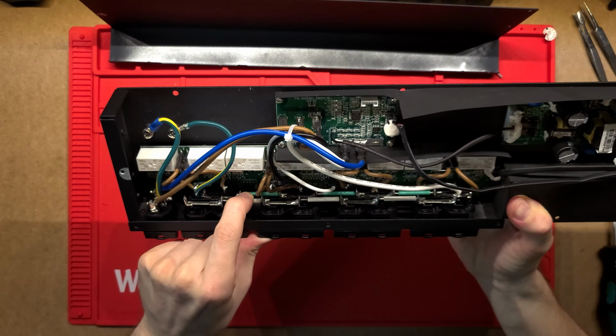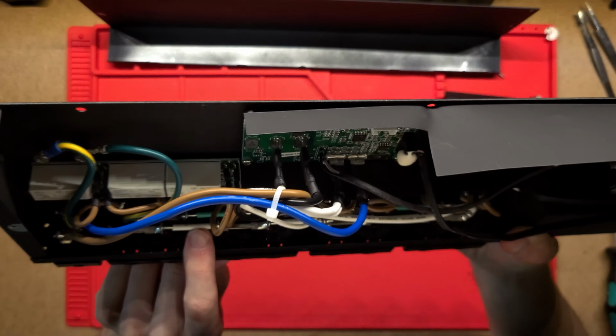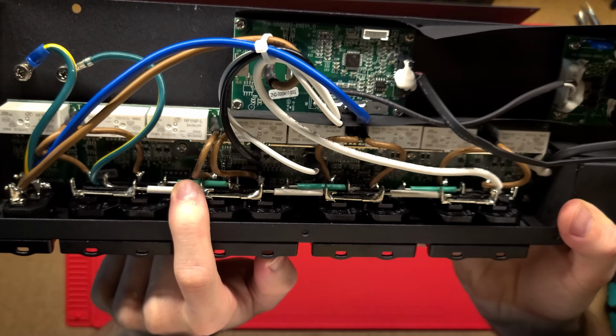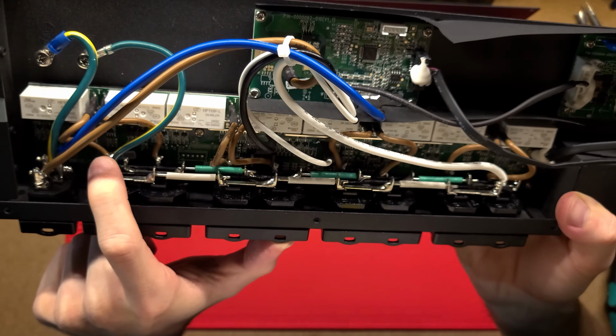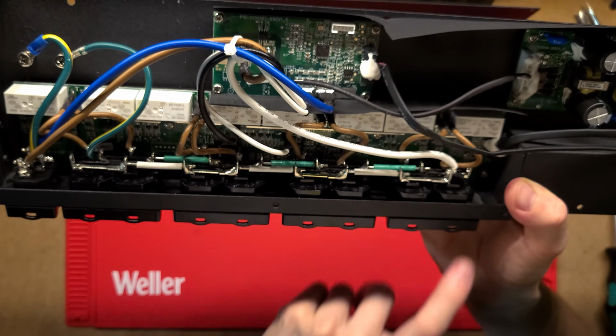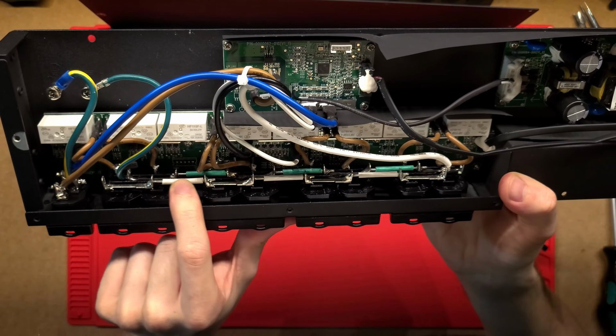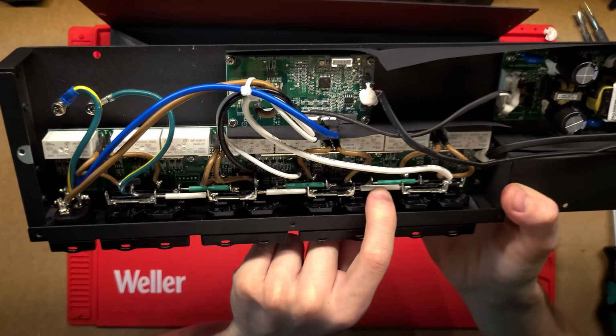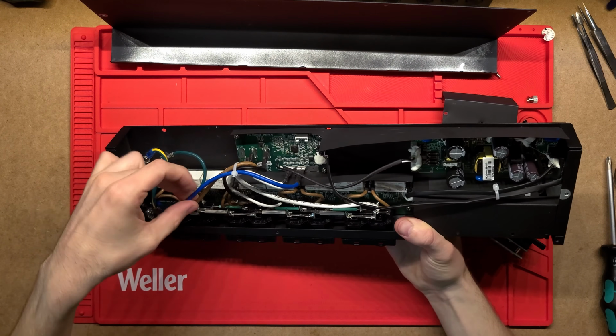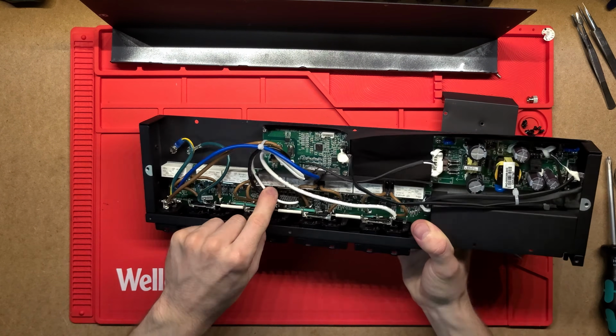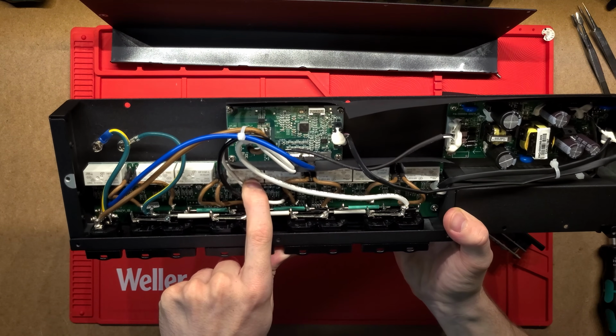So what I was saying before is up here we've got this green wire - it's quite a solid, thick wire that gets soldered in. That green is going to be the earth, and it goes from the left side here all the way across to the other side. We've got the same with the neutral, the white one. And the brown is the live one, and that's what's getting switched through these relays.